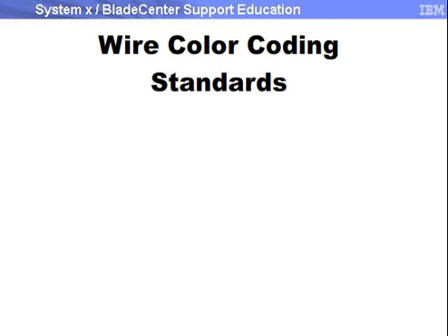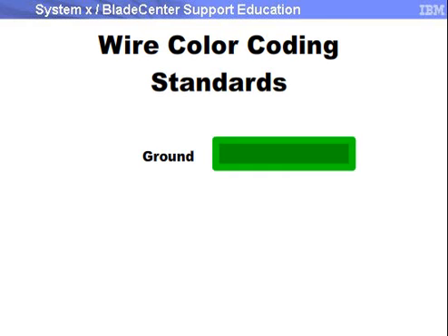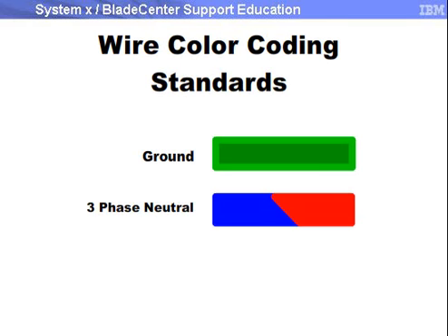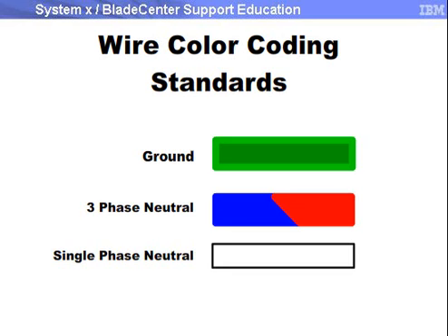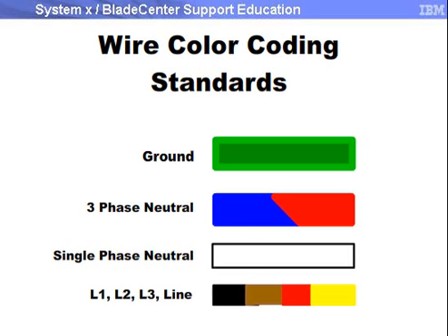As a general rule, typical electrical standard color codes are as follows. Ground wires are green, 3-phase neutral wires are blue or red, and single-phase neutral wires are typically white. Supply wires are colored other than the ground or neutral colors of the appropriate phase. Check with the local electrical codes in force to determine proper color coding.